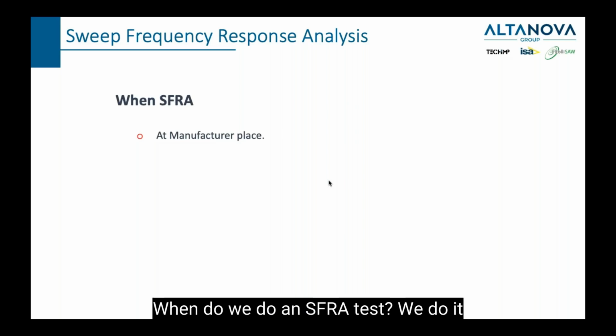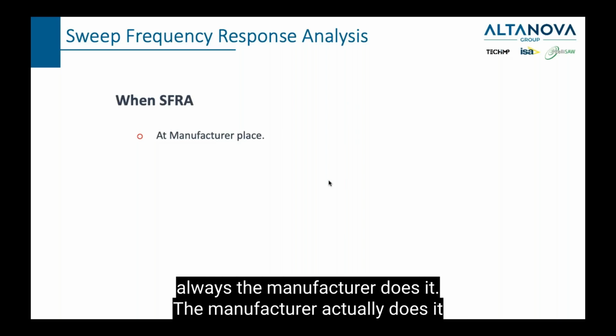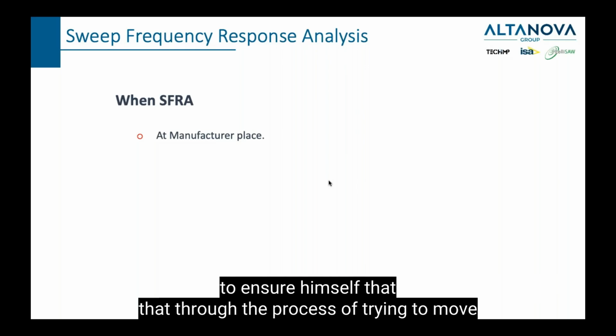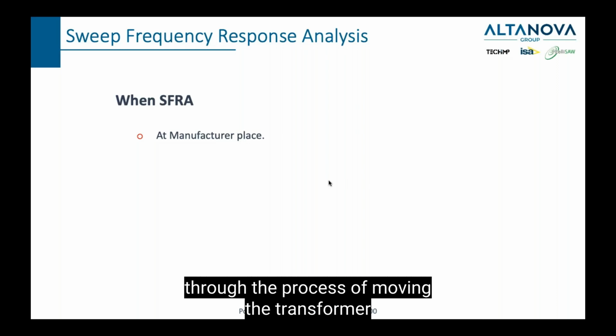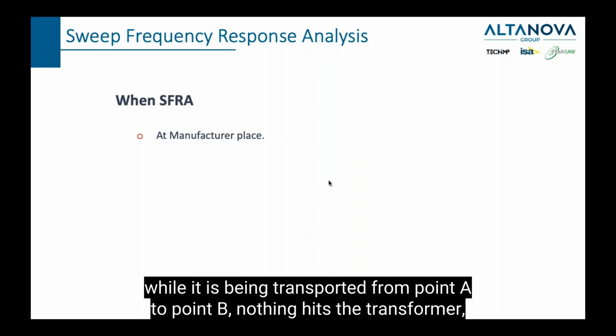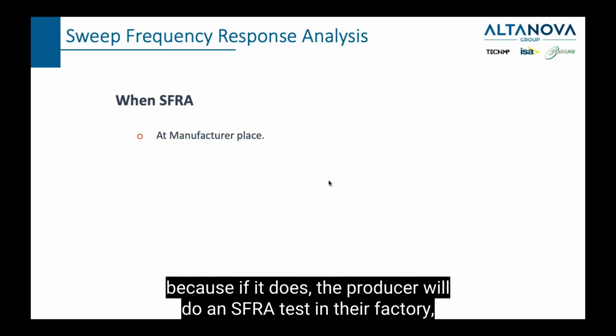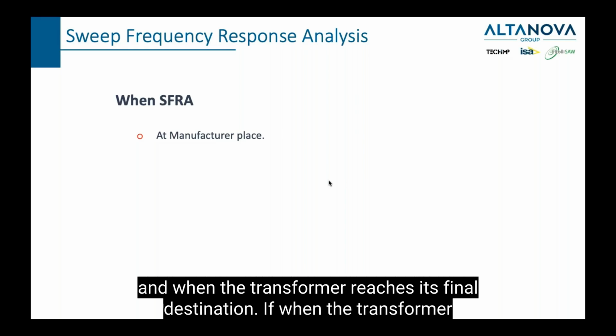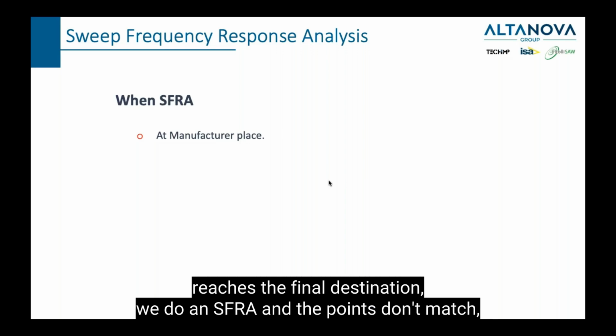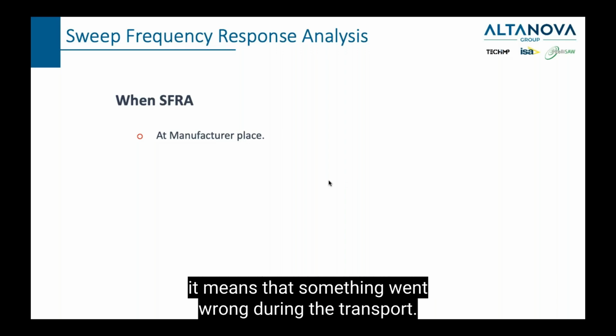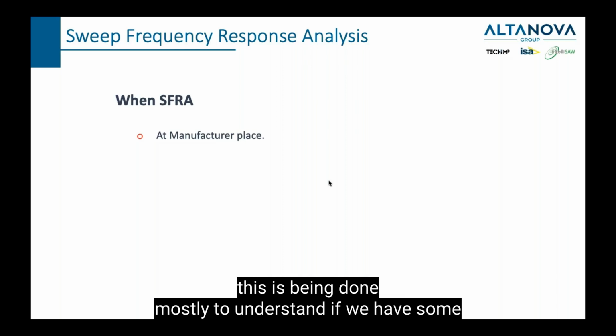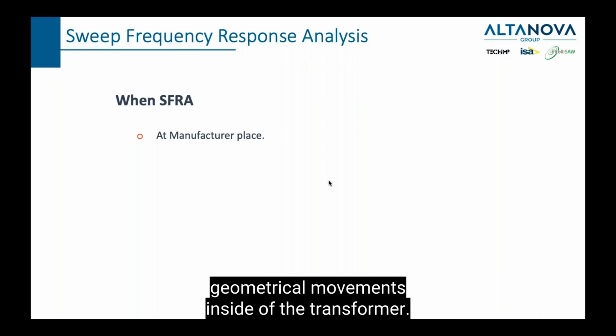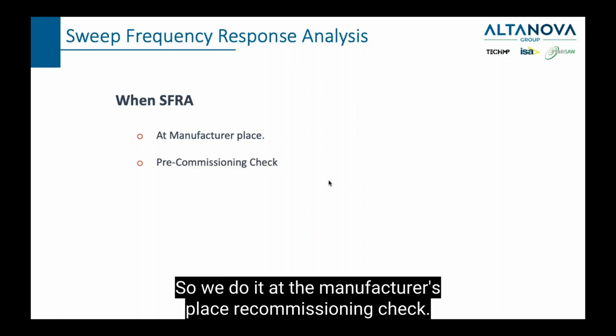When do we do an SFRA test? We do it always, the manufacturer does it. The manufacturer does it to ensure that through the process of moving the transformer, while it is being transported from point A to point B, nothing hits the transformer, because if it does, the producer will do an SFRA test in their factory, and when the transformer reaches its final destination. If, when the transformer reaches the final destination, we do an SFRA and the points don't match, it means that something went wrong during the transport. Let's not forget, once again, this is being done mostly to understand if we have some geometrical movements inside of the transformer. So we do it at the manufacturer place, pre-commissioning check.